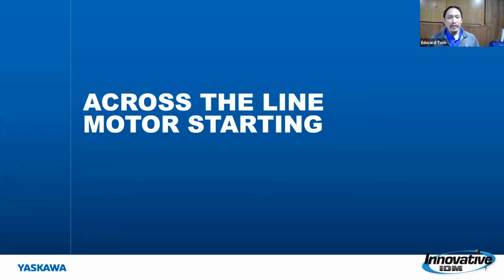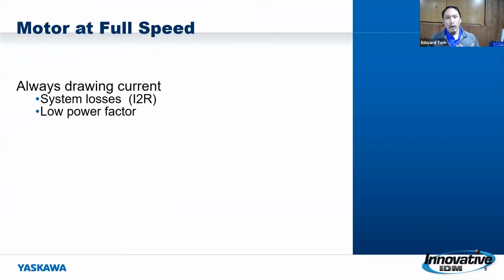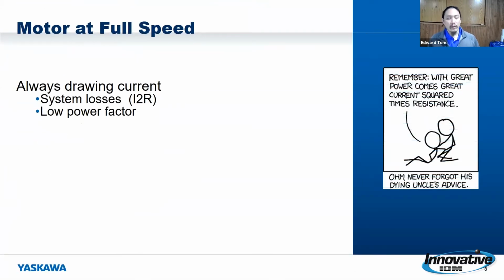Some of the things about running a motor across the line: when a motor's running at full speed or across the line, it's always drawing current. It needs current to be able to magnetize and start spinning that rotor. But when you have that current running through there, you're going to get system losses. If you've got current running through the line and through your wires, there is some resistance, and that is going to result in some of the losses just to get from point A, from the power company, all the way over to your machine.